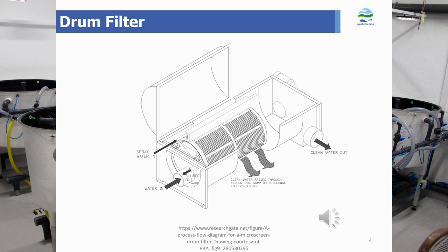It is important that the velocity of the outlet drain pipe to the drum filter should be above 0.3 meters per second to ensure solids do not settle in the pipe. However, if the velocity is too high — over 1.5 meters per second — particles may break up into smaller pieces and become more difficult to clean. The pipe slope should be set to guarantee water velocity between 0.3 and 1.5 meters per second.